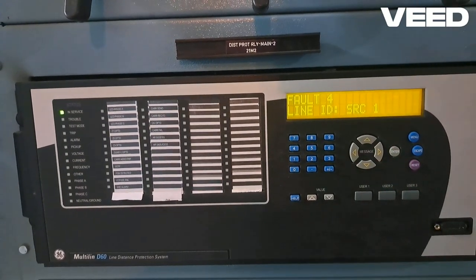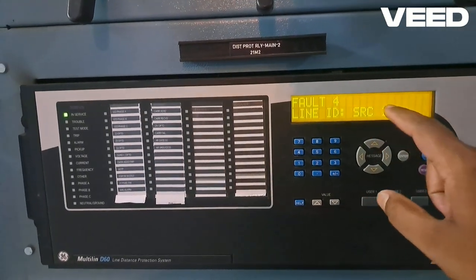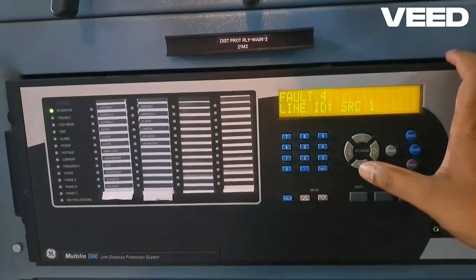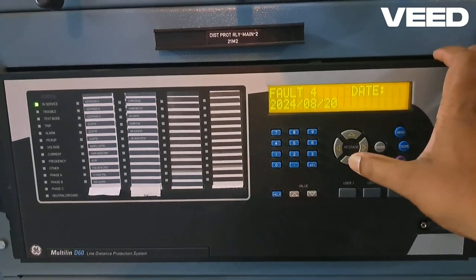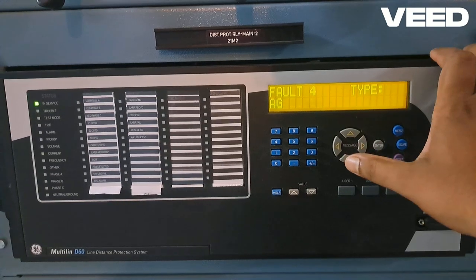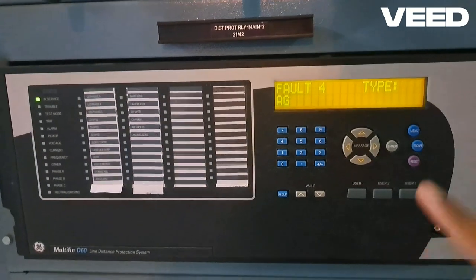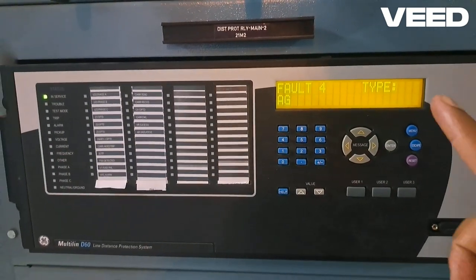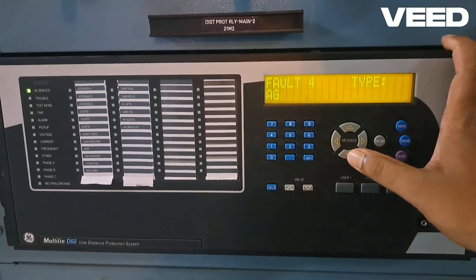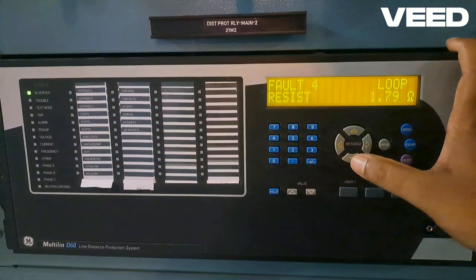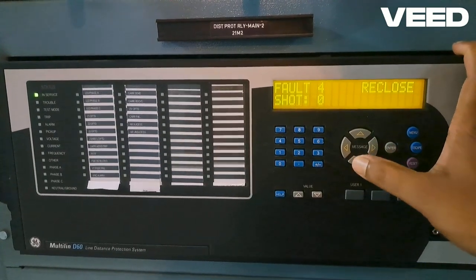Then again I will use the right arrow. Here I have fault four and the information about fault four is written below. I will use the down arrow key to see the different parameters — here I have the date, here I have the time of the fault. AG fault is written not in terms of R/Y/B but instead in terms of ABC; G is for ground fault. Here it shows the fault location, resistance, and reactance.